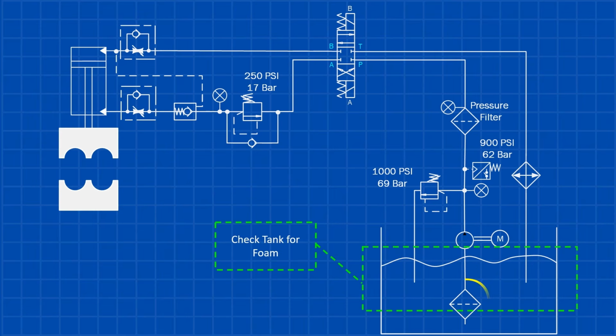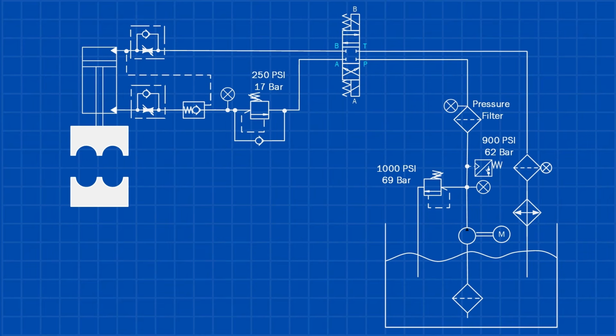Start by checking the tank for foam, as this is a sign that there's air in the system. This can happen if the suction strainer is clogged or if the pump is sucking air through a bad seal. If you find foam in the tank, clean or replace the suction strainer first. If that doesn't fix the issue, replace the pump and make sure it's properly aligned with the motor. If there's no foam in the tank, the next step is to replace the relief valve and check if the system can reach the set pressure. If you still can't achieve the correct pressure after replacing the valve, the problem is likely a failed pump, and it should be replaced.